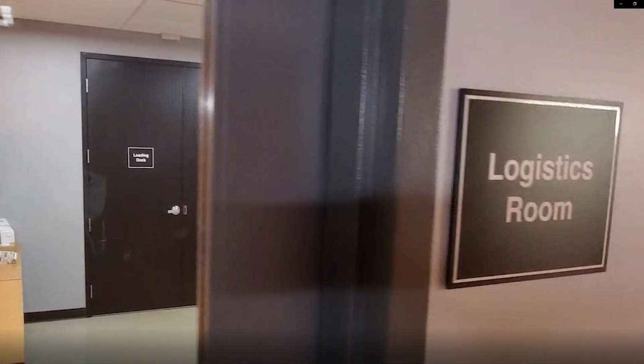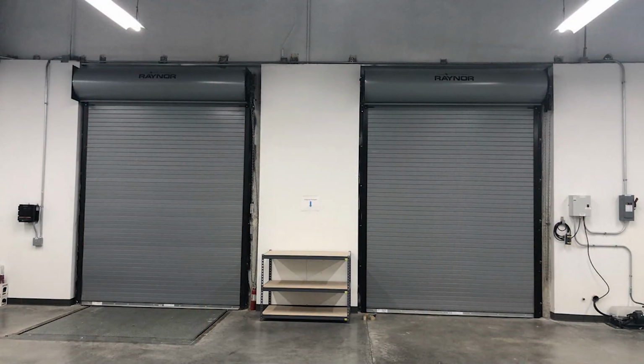The staging room can be utilized for setup and configuration of servers before delivery to the data hall. This area provides space to unbox and discard all cardboard, which is not allowed on the data center floor. Power outlets and power strips are provided for customer use. The loading dock area provides plenty of room for the delivery trucks to turn and back into the dock bays. One is equipped with a lift to accommodate different truck heights. The loading dock provides 3 bays for receiving equipment and is managed by DataBank personnel. Clients do not have to be present for us to receive your delivery.